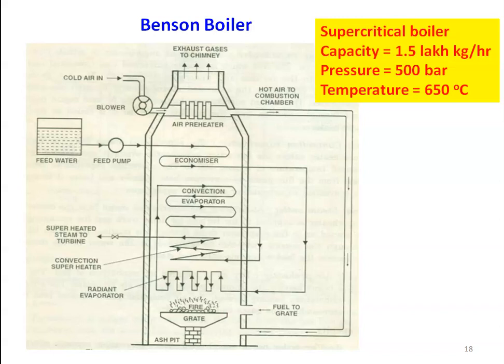This is also called a supercritical boiler. When the pressure of the steam is higher than 221 bar, it is called a supercritical boiler. Normally for very high capacity steam generation, we use the Benson boiler or supercritical boiler. The pressure is around 500 bar, the temperature is 650 degrees Celsius, and the capacity of the Benson boiler is 1.5 lakh kilograms of steam per hour. This is the Benson boiler — a once-through, supercritical boiler.